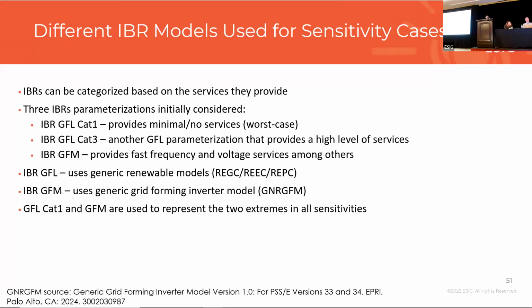They are only going to be injecting active power. If they are operating at a non-unity power factor, then they are going to be injecting constant reactive power all the time into the system and not really going to change that. They're the worst case scenario, because they provide no service at all to the network. If you want to link it to a power flow context, think of it as your PQ buses in a power flow context, where P and Q are fixed, and irrespective of what changes in the network, that P and Q will not change. So they are the worst case.